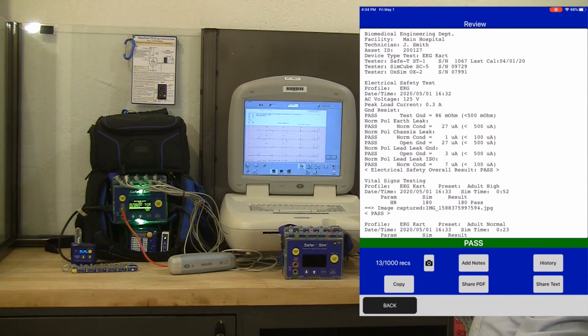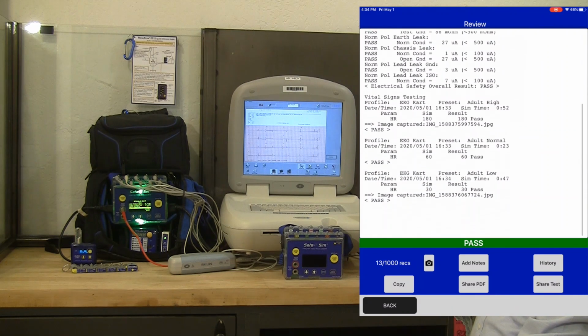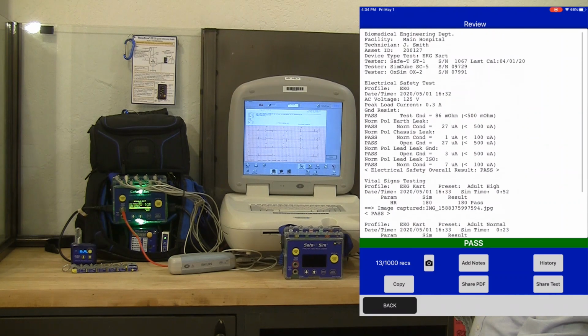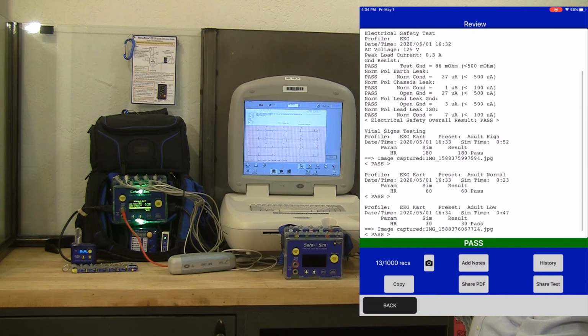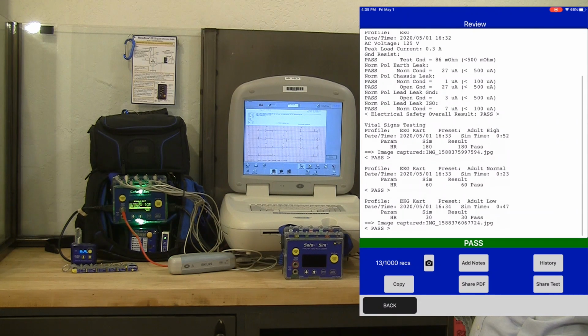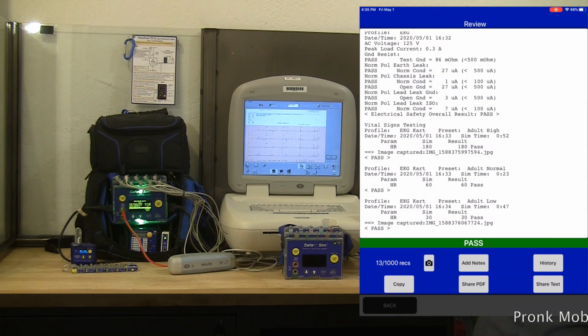We've got all the detail we need in an electronic record, including the facility, the technician name, the asset ID that we were testing, that we barcode scanned, all of our test devices, serial number, model number, cal date, each of the individual electrical safety tests that we ran, as well as the pass-fail limit and the measurement that was taken, and then my low, mid, and high heart rates are also recorded as a result and pass-fail.